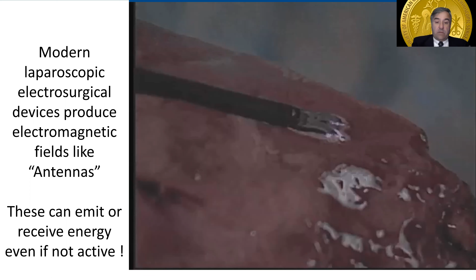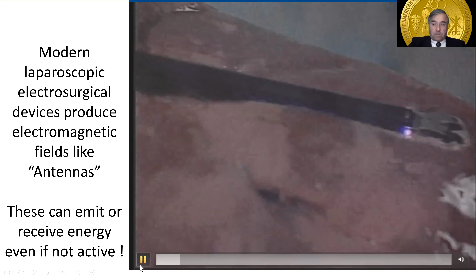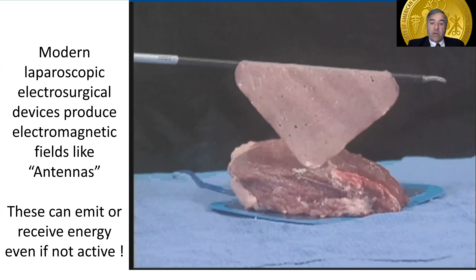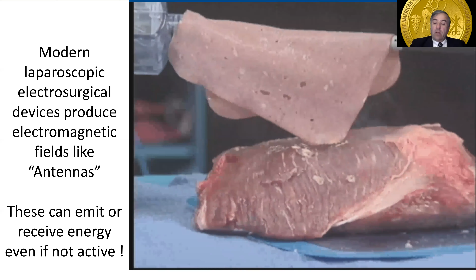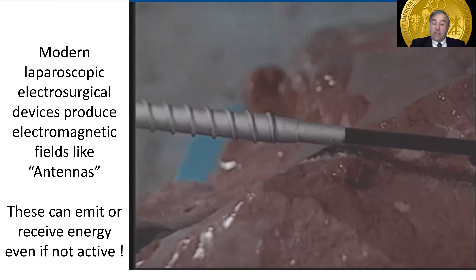The surgeon has to understand this concept if he wants to prevent inadvertent burns. This is especially true with the long laparoscopic instruments, as shown here. They act like large antennas, perfect receivers and perfect emitters of energy through the electromagnetic field in your operating field. And this video will illustrate this. So here you have a long laparoscopic instrument, and you can see how the energy through the insulation is transferred to the tissue outside of the active area of the electrode. And this happens even through tissue that's wrapped around this electrode, as you can see here. So just imagine this is bowel wrapped around your laparoscopic instrument or your cannula.